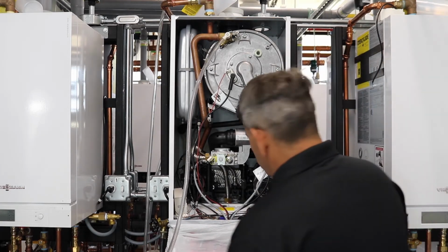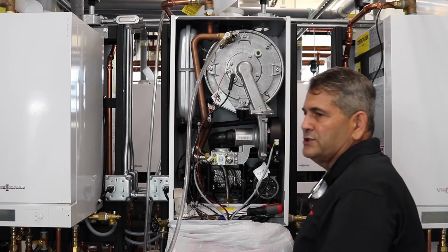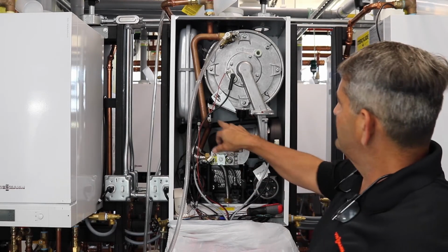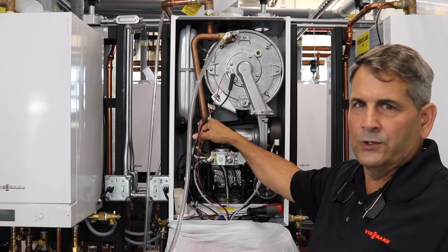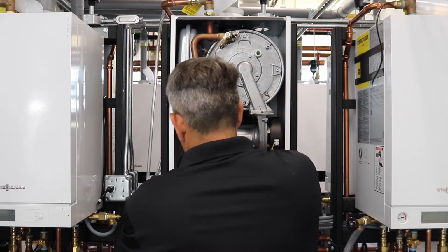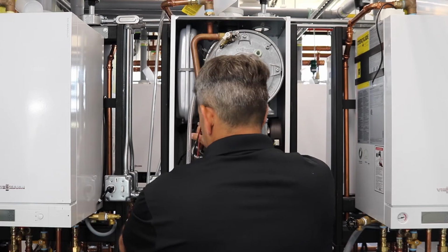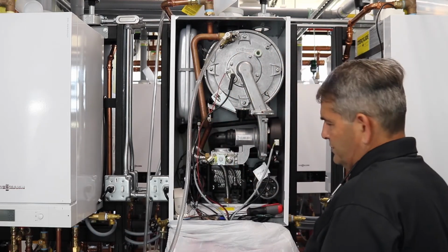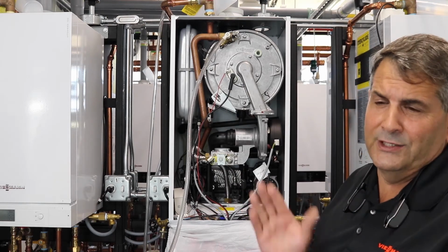So what we're going to do now is make sure we isolate the boiler, and we're going to drop our pressure on the boiler. Basically, here's our flow switch. So we're going to just drop the water, and there's only a gallon of water in this boiler. What I like to do is open up my valve and start to drain it, and we'll drop the pressure. You can watch your gauge in the front, but remember, we have it isolated so that gauge won't move.